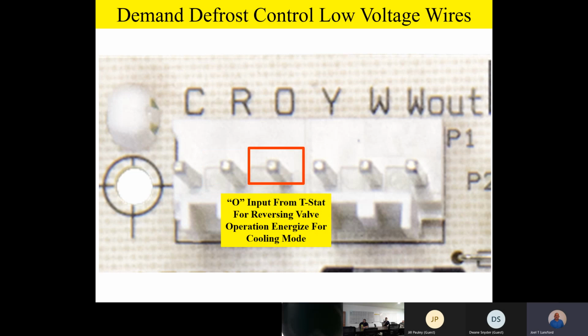The O terminal is an input from the thermostat for reversing valve operation. Now, it should be noted on our Champion equipment, anytime we energize the O terminal, we're going to be in the cooling mode of operation. So O is our input from the thermostat for reversing valve operation to switch to cooling mode.